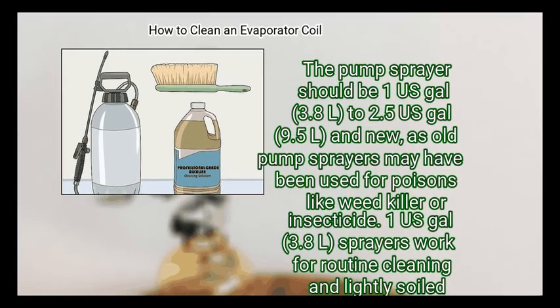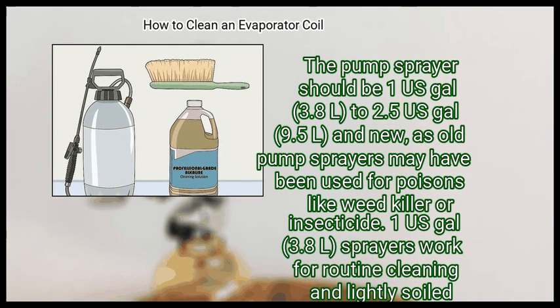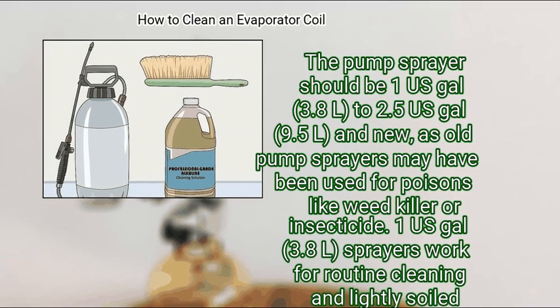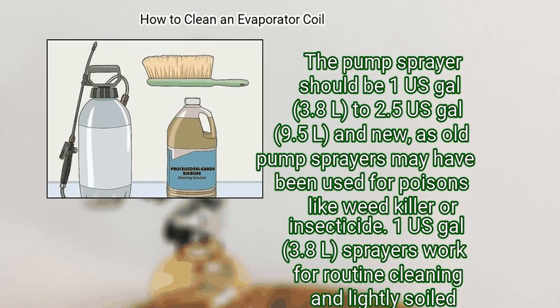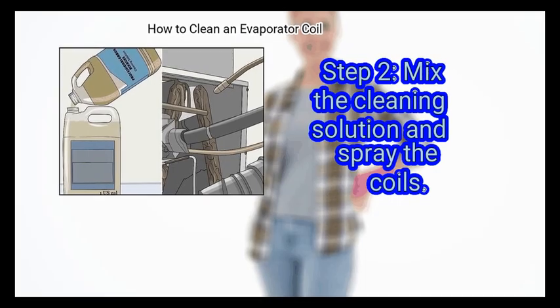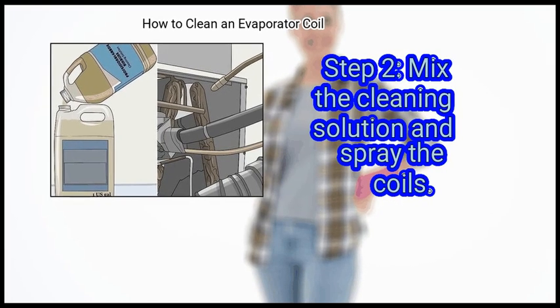The pump sprayer should be 1 US gal, 3.8 L, to 2.5 US gal, 9.5 L, and new, as old pump sprayers may have been used for poisons like weed killer or insecticide. 1 US gal, 3.8 L, sprayers work for routine cleaning and lightly soiled coils, while larger sprayers are best for heavy cleaning.